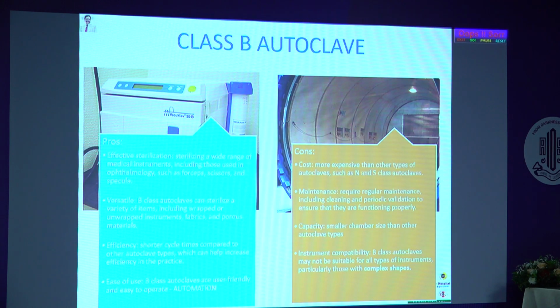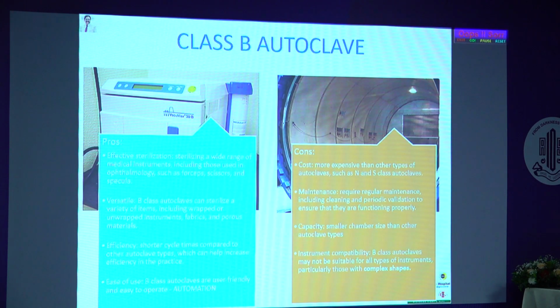And ease of usage. Most of the Class B autoclaves are automated and easy to use. We can also have control over the way it is handled. The cons part is that it's a bit expensive, and it needs regular maintenance and good quality water. This is very, very important. Having purified water is important, and for the wrapping, you should not use cloth. Most of the problems happen because it is improperly wrapped with cloth, where the fiber is released and gets clogged into the drainage area. And compatibility is very, very important. So you have to use common shape instruments. A large instrument will be difficult.